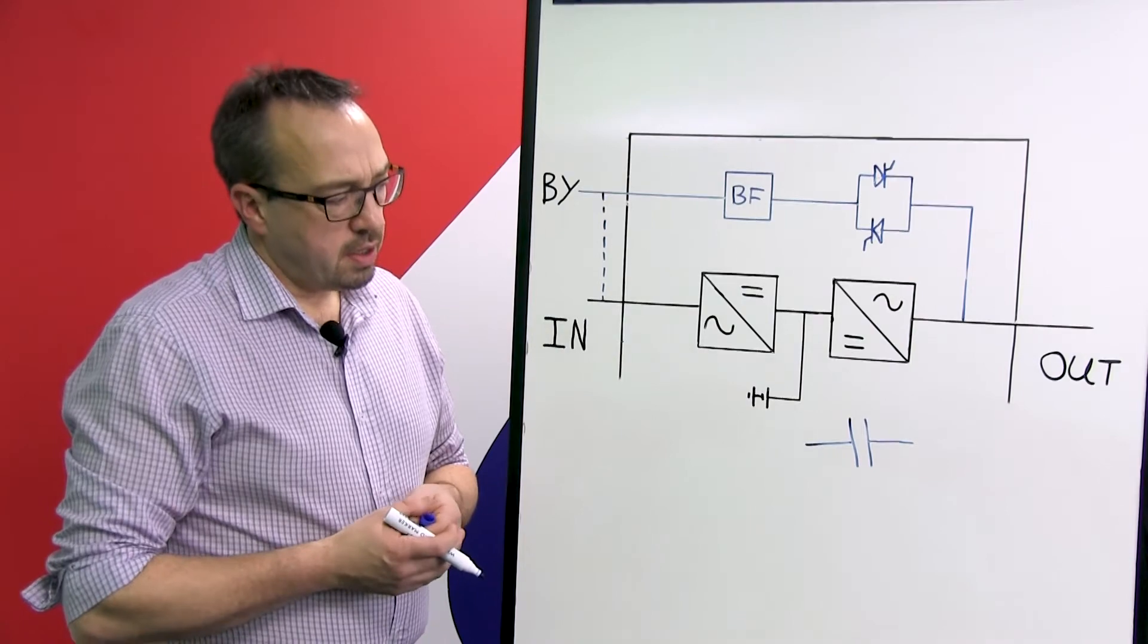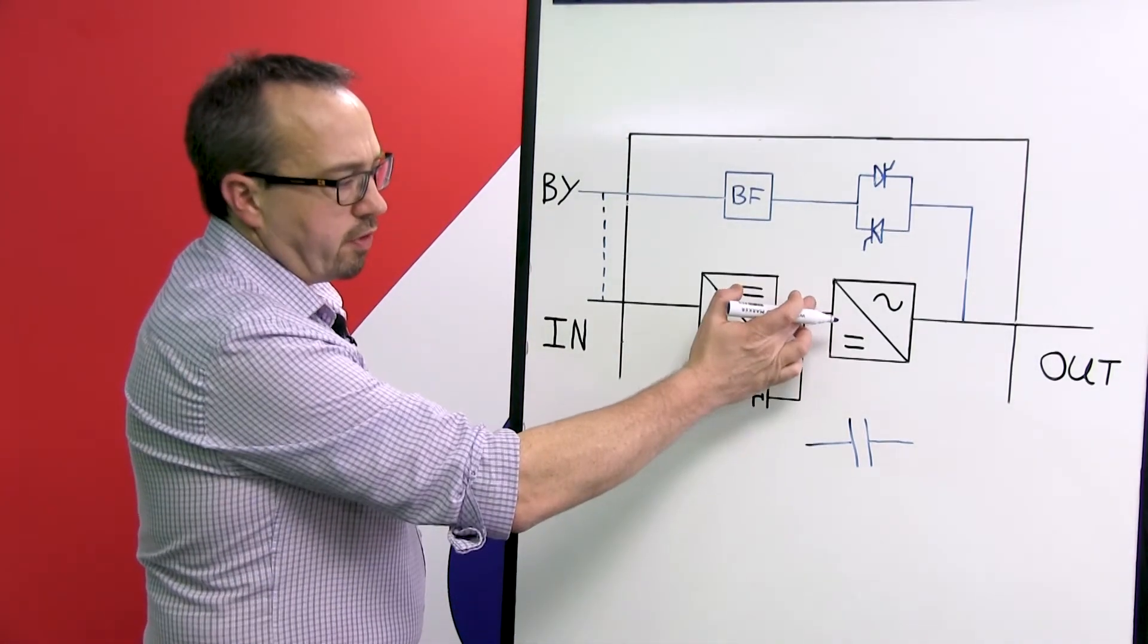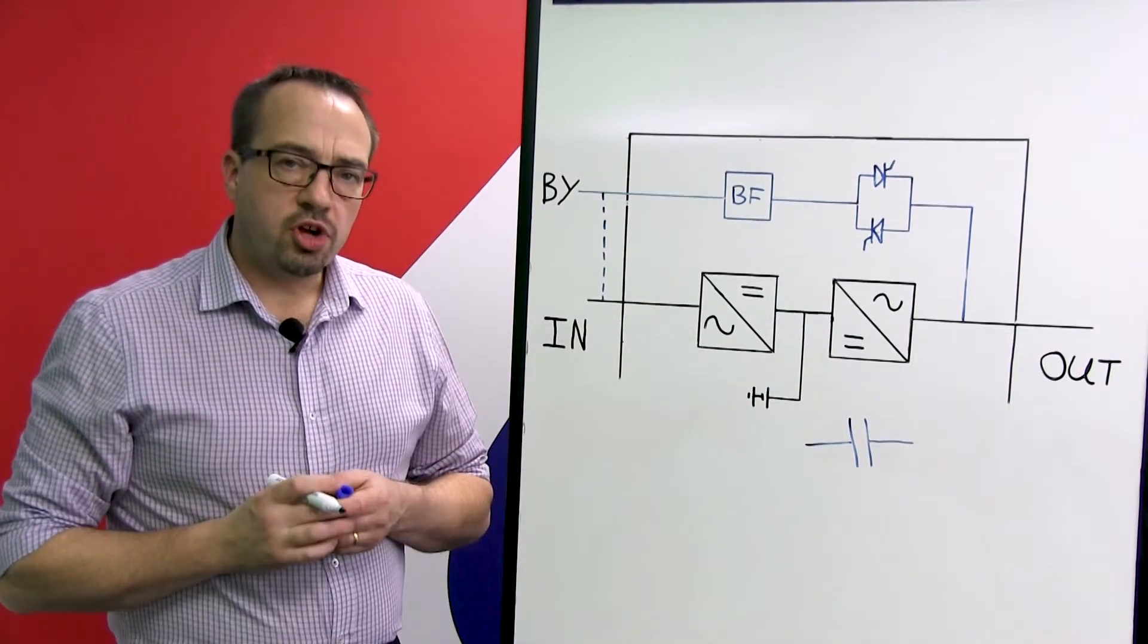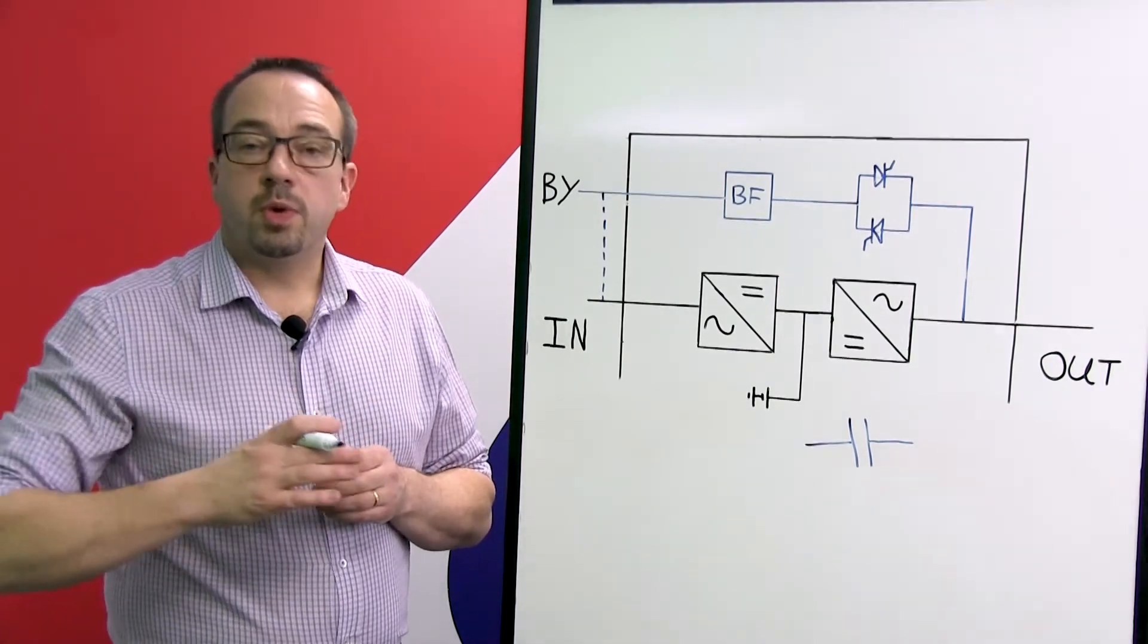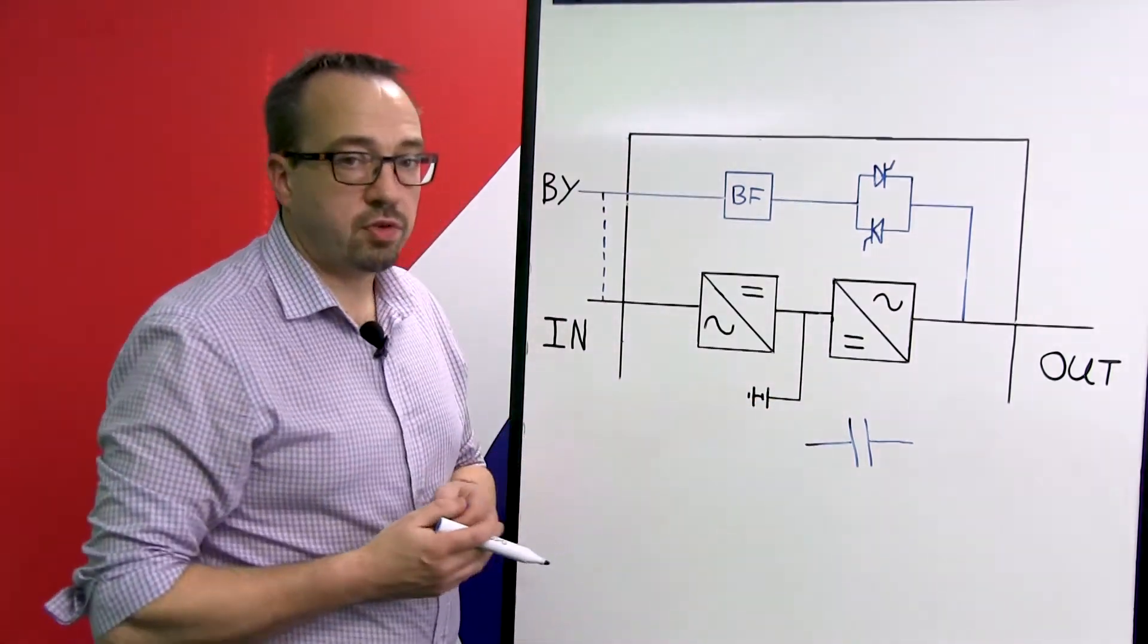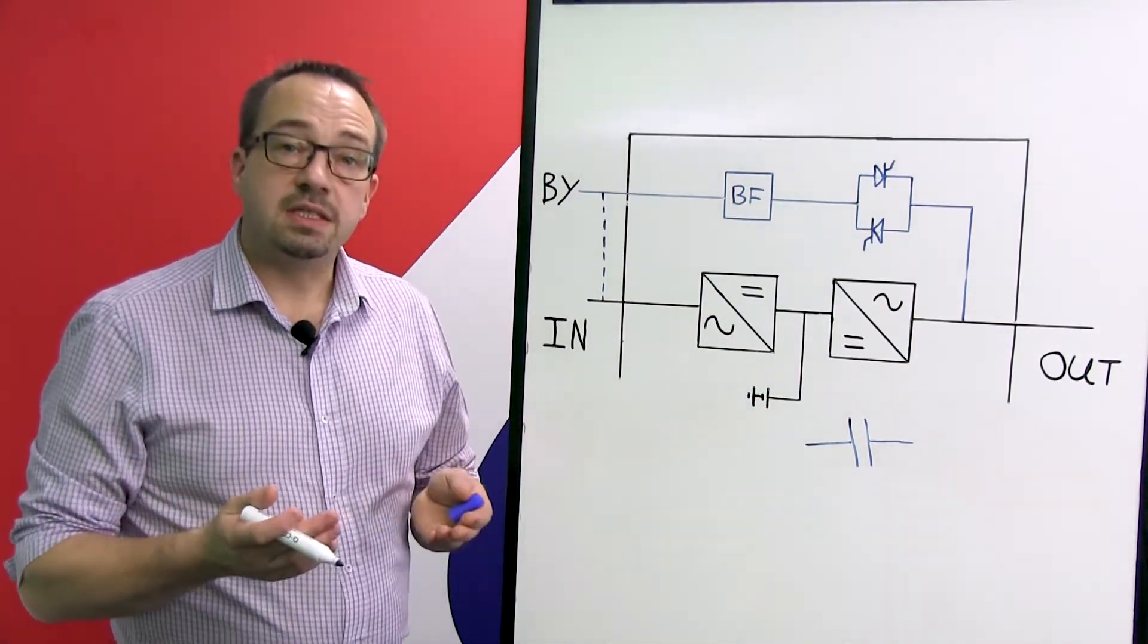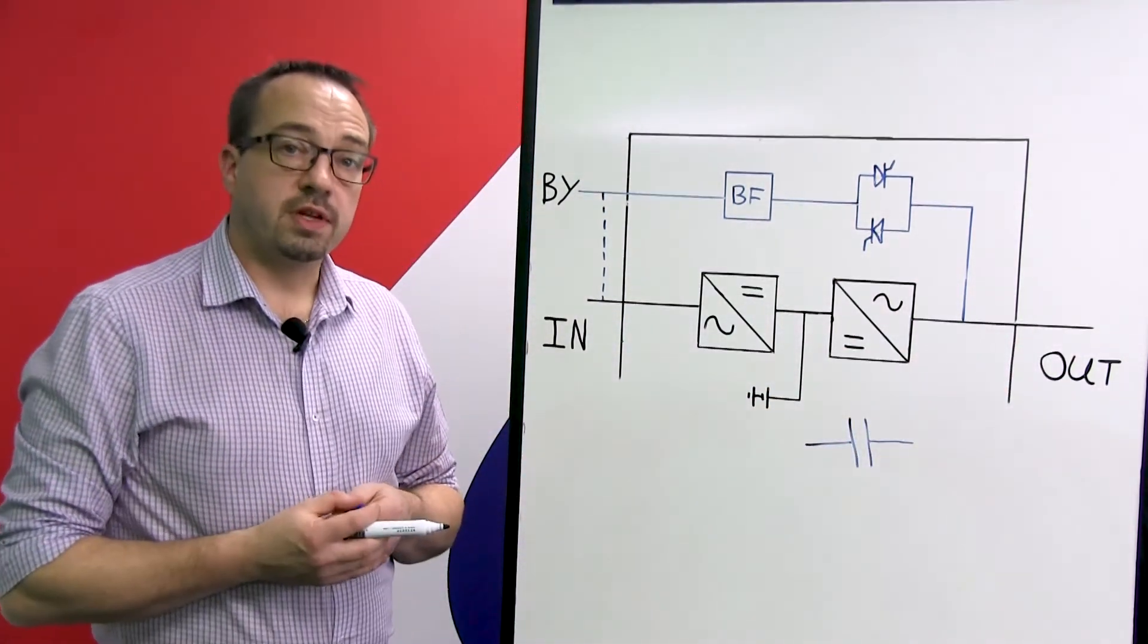The purpose of a capacitor is to ensure that whilst we are transferring between the rectifier output and onto the batteries, the capacitor will hold up that DC rail for a long enough time so that we can make that transfer and the inverter does not see any disruption in the source of electrical power. Therefore, the inverter can continue operating and hence continue providing the protected load with a clean source of electrical power.